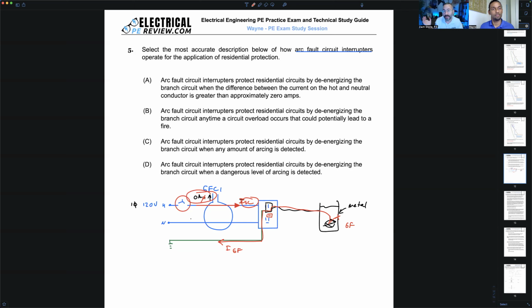It could be a quarter of an amp, it could be half an amp. It's going to detect right away that, hey, we expect all of our current to come back on the neutral. It's not, but I still have current flowing into the circuit. We got a ground fault somewhere, trip right away. So it's going to help your breaker trip when sometimes your ground fault current might not be large enough to trip the instantaneous trip setting on your breaker.